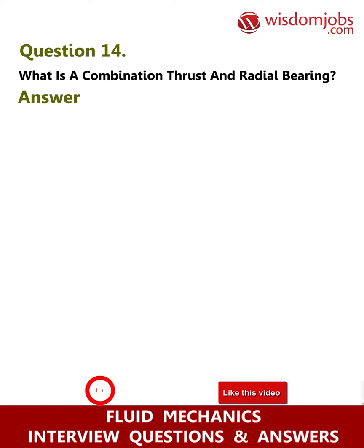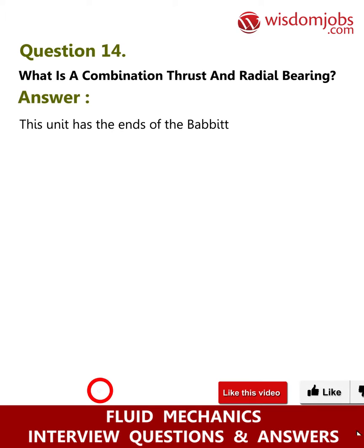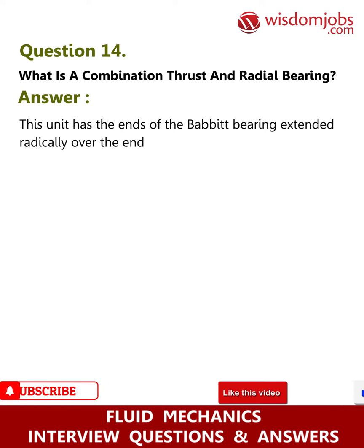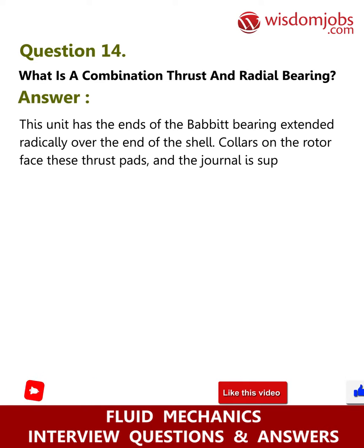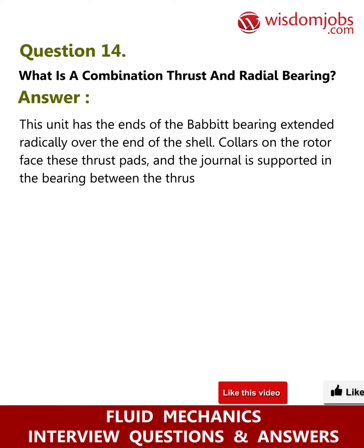Question 14: What is a combination thrust and radial bearing? Answer: This unit has the ends of the babbitt bearing extended radially over the end of the shell. Collars on the rotor face these thrust pads, and the journal is supported in the bearing between the thrust collars.